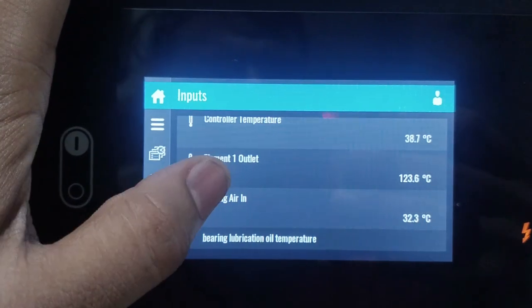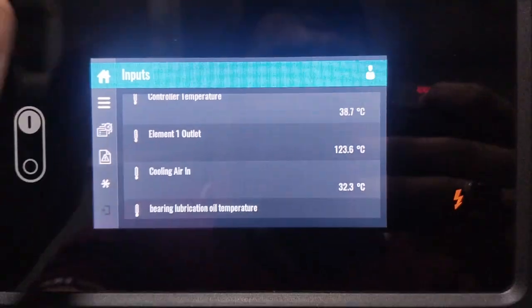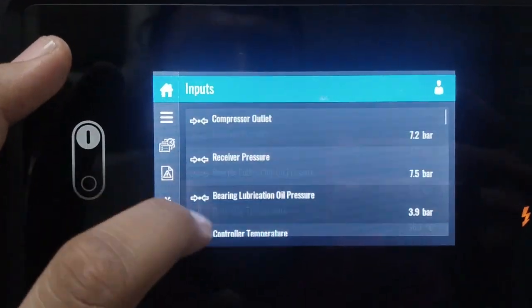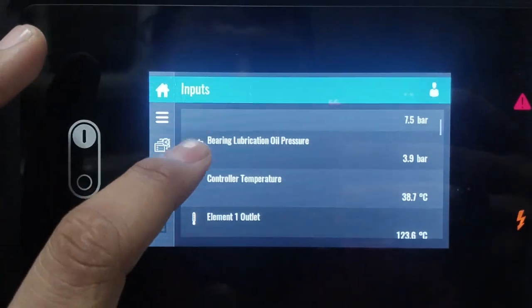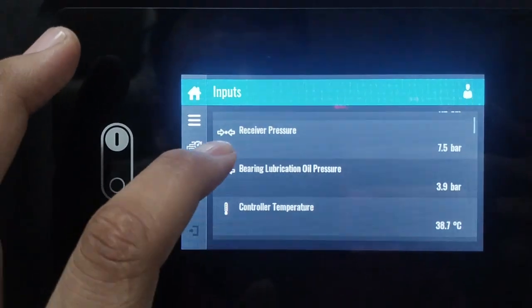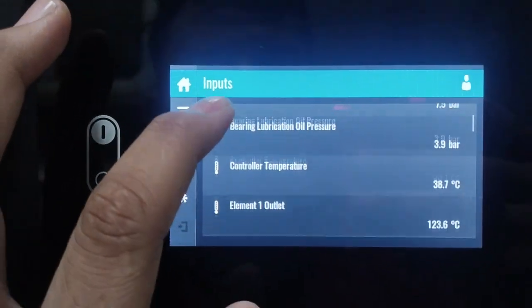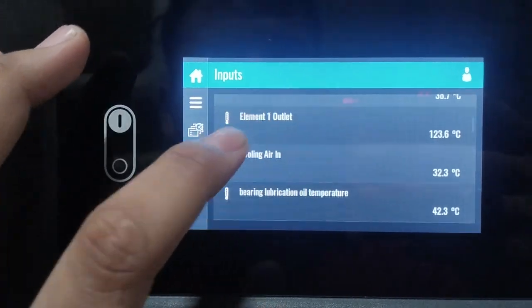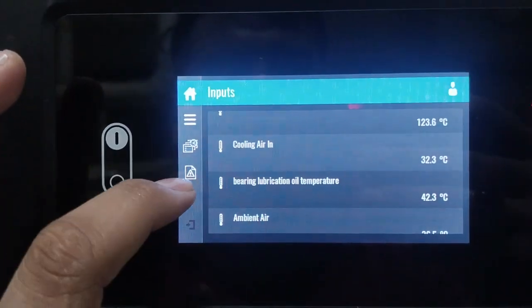As you can see, only the compressor outlet temperature was very high — that is the reason this compressor is on shutdown. This clearly shows that the compressor was forced to stop automatically to protect itself from overheating. Now the big question is: why does this happen?